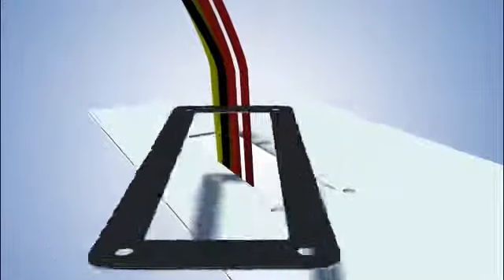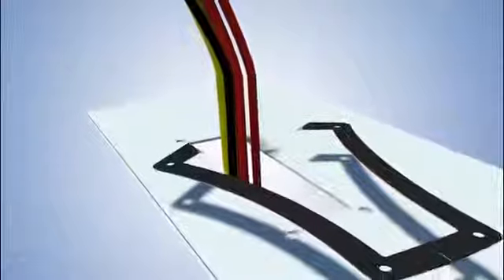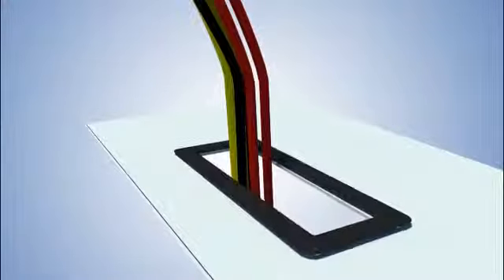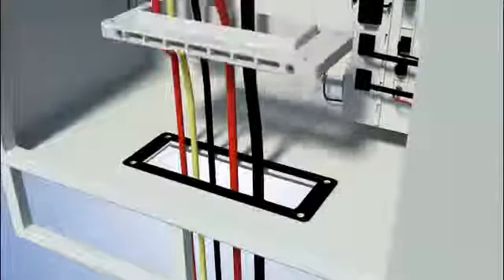You need to subsequently take in all the cables within the back gasket by always making an angular cut with the blade first. Fix up the back gasket on either side of the RFCS frame or on the cabinet surface by just matching the mounting holes. Thereafter, fix the RFCS frames firmly on the cabinet cutout by tightening with the mounting hardware supplied with the complete RFCS kit.